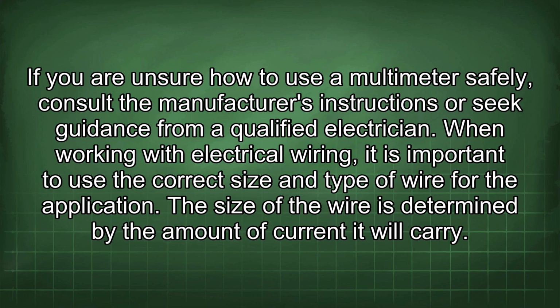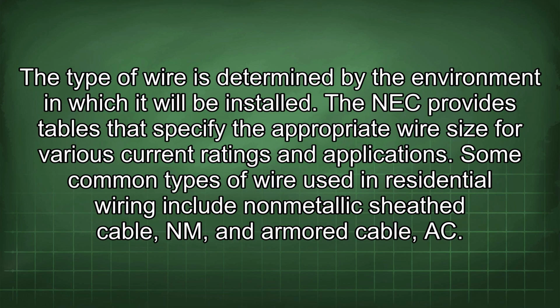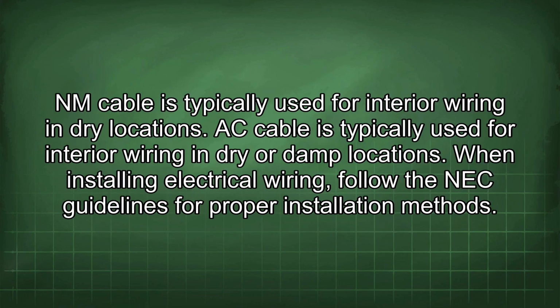When working with electrical wiring, it is important to use the correct size and type of wire for the application. The size of the wire is determined by the amount of current it will carry. The type of wire is determined by the environment in which it will be installed. The NEC provides tables that specify the appropriate wire size for various current ratings and applications. Some common types of wire used in residential wiring include non-metallic sheath cable, NM, and armored cable, AC. NM cable is typically used for interior wiring in dry locations. AC cable is typically used for interior wiring in dry or damp locations.